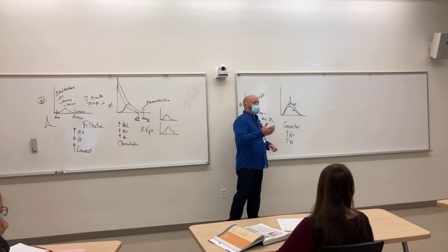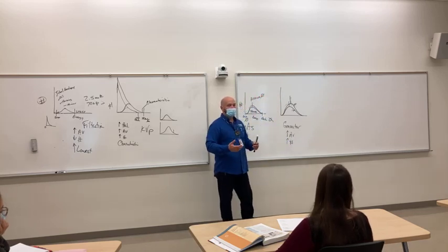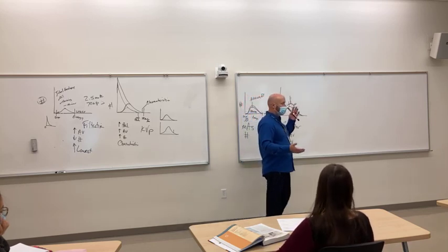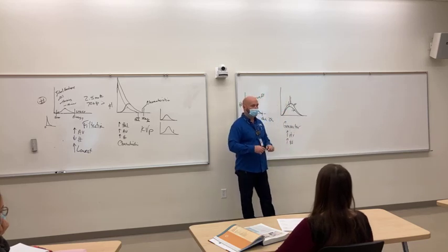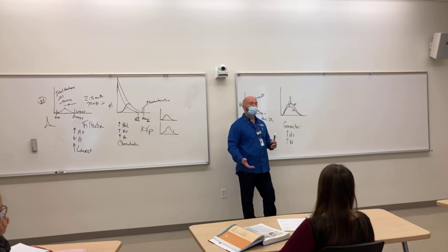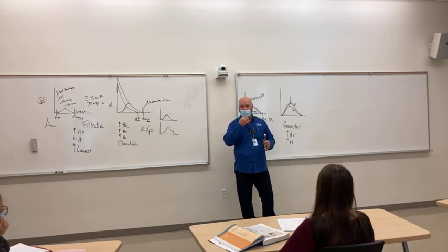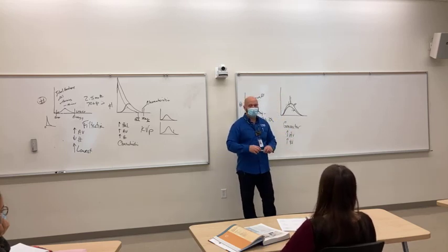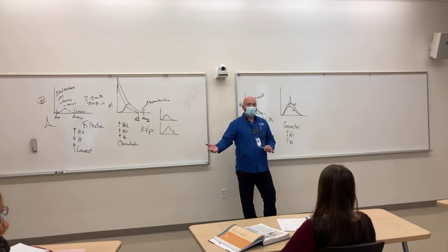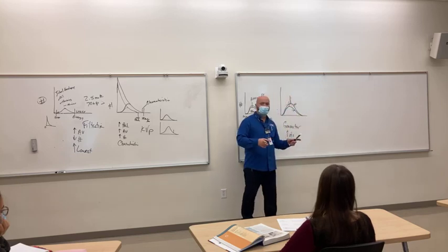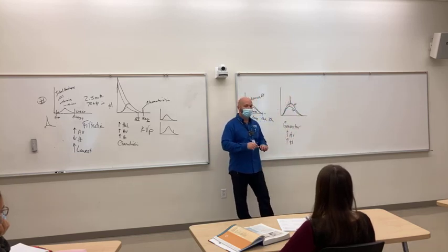So you're probably in your career never going to see this. I've been unfortunate enough to work in a hospital that, in the ER of all places, had a single phase room right next to a high frequency room. Nightmare scenario, because the techniques are so greatly different. One was phototimed, and even though it was a high frequency room, it was a doctor's office type machine that they scrimped and put in the ER. The other room was an unphototimed single phase room, okay? So if you knew a technique for one room, then you had to convert it to go into the opposite room.